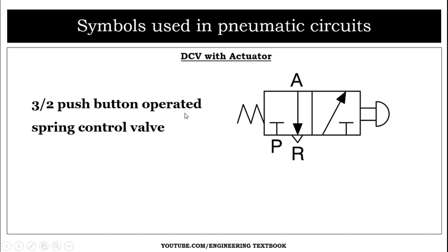This valve is push button operated with a spring return. When we press the push button, the valve moves to the actuated position. When we release the push button, the compressed spring releases and the valve returns to its unactuated position. This is the three-by-two push button operated spring return control valve.